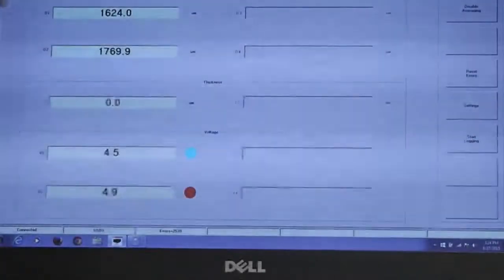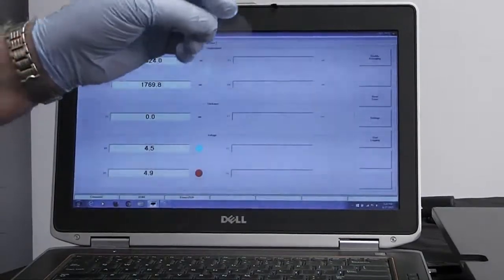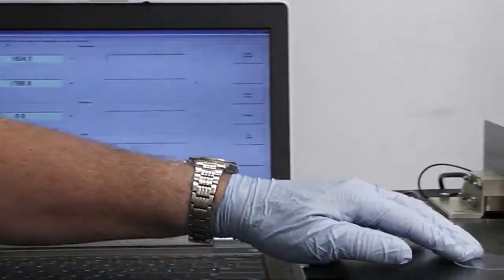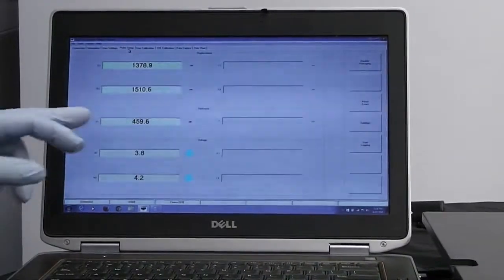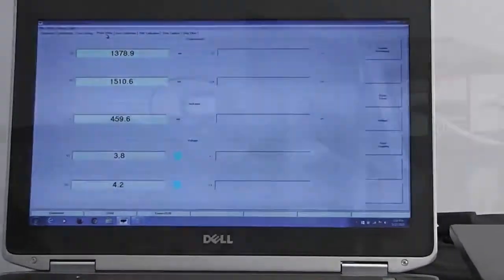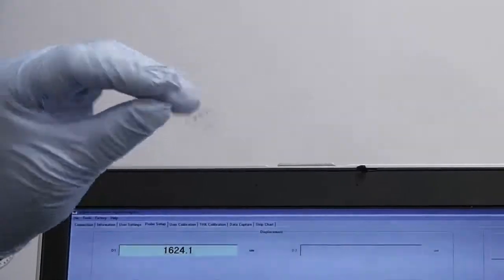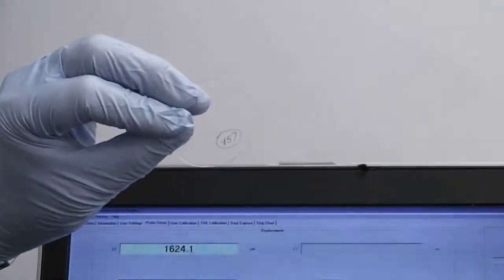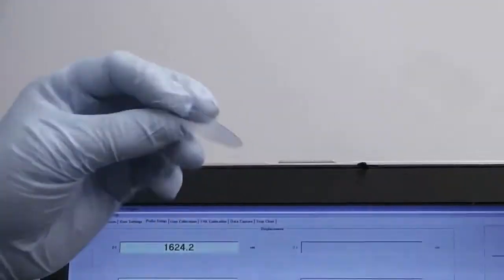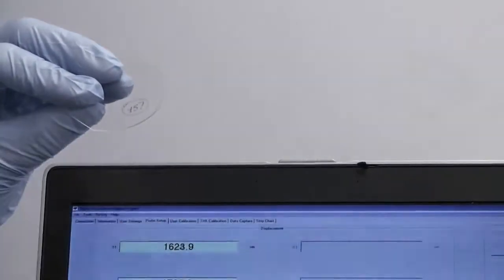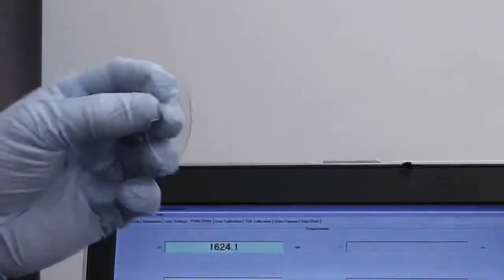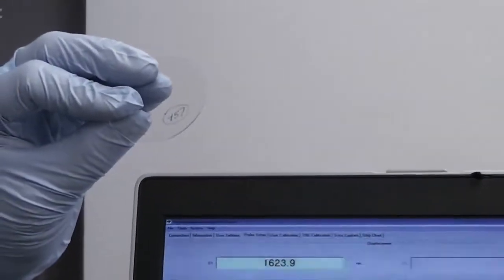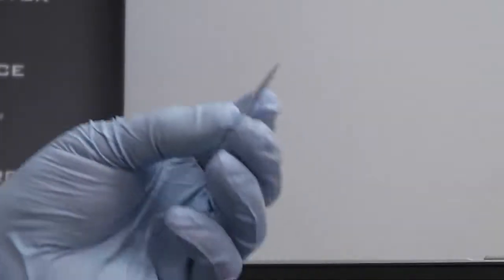I also have another smaller wafer here from another manufacturer. This one's 457 microns. It's a little tough to see because it's clear. I'm sliding that under there. And we're reading 459 microns. And these, interestingly enough, these sapphire wafers which look totally flat actually have about a 2 to 3 total thickness variation over the surface. And that's what the manufacturers are actually trying to see. They want to find out if there's a lot of variation across the surface in the wafers. Because these things can turn into LEDs. And that kind of difference, or a difference of 10 microns, can be the difference between a good LED and a bad LED.